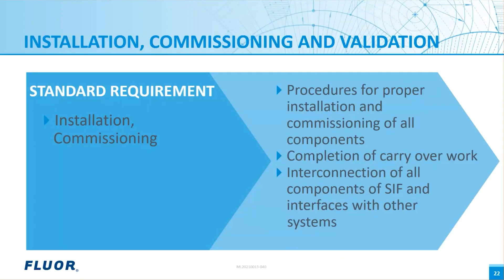But some of the important points for this phase, what I would recommend, are: ensure that all the equipment is installed in line with the procedures and there is no damage caused in transportation. These checks need to be done both before and after the system installation and interconnections. All the carryover work from the factory acceptance testing should be completed and the records updated. All the field equipment and interfaces of SIS, for example BPCS, fire and gas, BMS, should be connected and operational. Ensure that all the commissioning records are properly documented. And lastly, all the non-conformances need to be resolved before you declare that the system commissioning is completed.